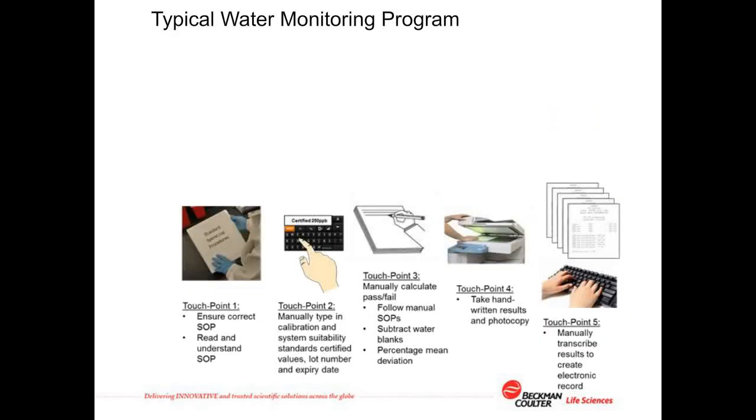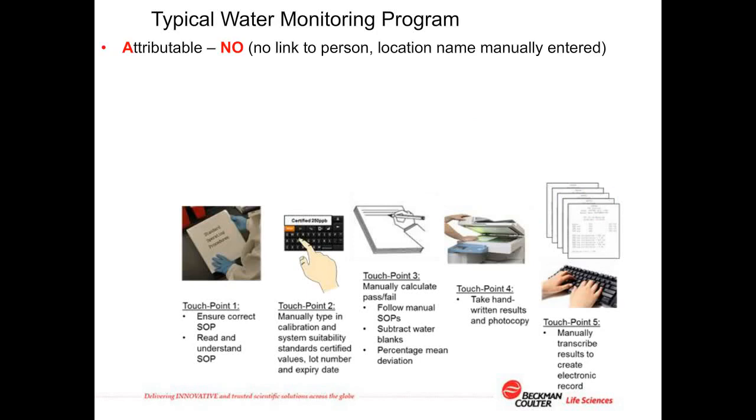Now let's take a look at the current water analyzer practices in the light of the FDA ALCOA guidance. There are many manual steps in the typical process, and usually the paper record does not contain an electronic signature, so it's not attributable to the technician.